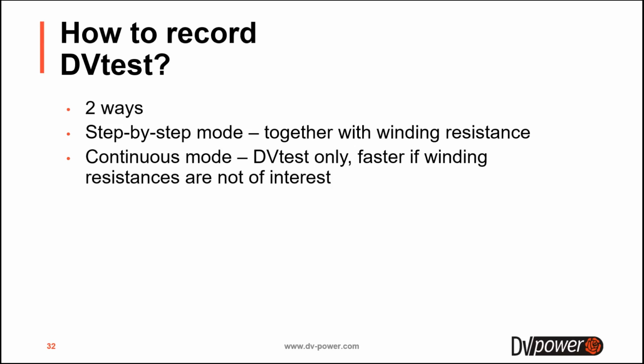Another way is so-called continuous mode. And in this mode, you can record only DVtest without winding resistance. So what does it mean? You inject a DC current through the winding and through the OLTC, start recording that current, and simply operate the tap changer quickly from first to the last tap position. So in that way, you are just recording a DVtest graph. You are not measuring winding resistance. So we call it continuous because we are continuously recording DVtest. And this is a faster way to do that because you are not measuring winding resistance. You are not waiting for the stabilization of winding resistance results.